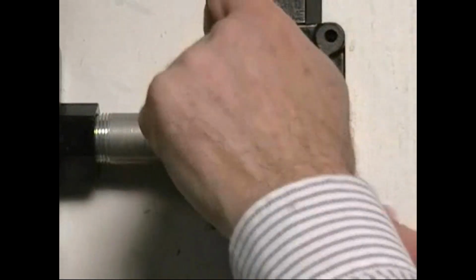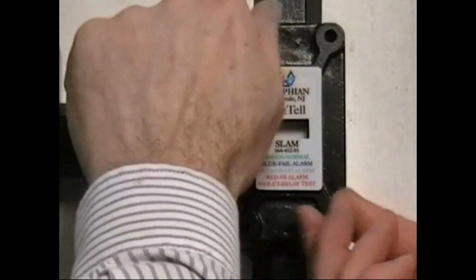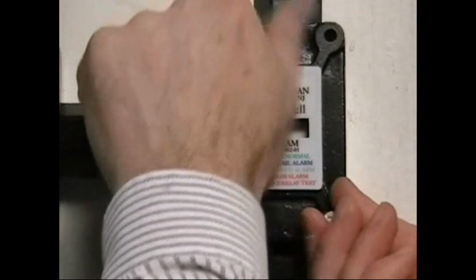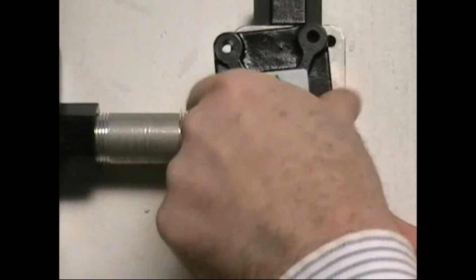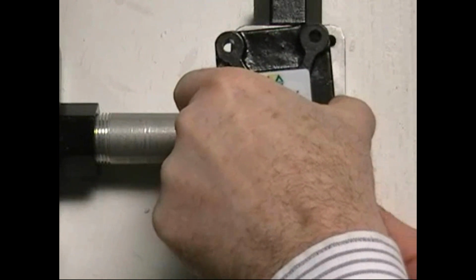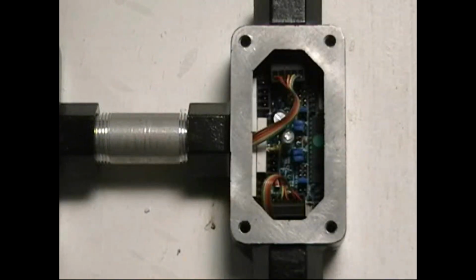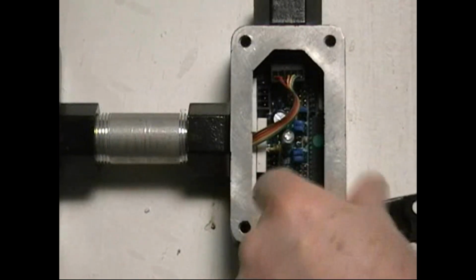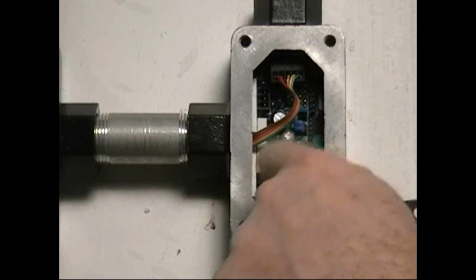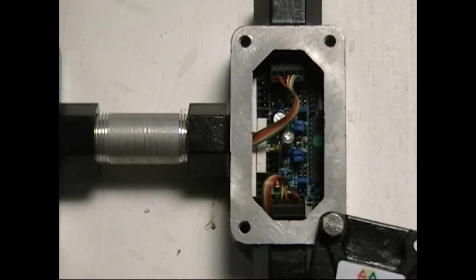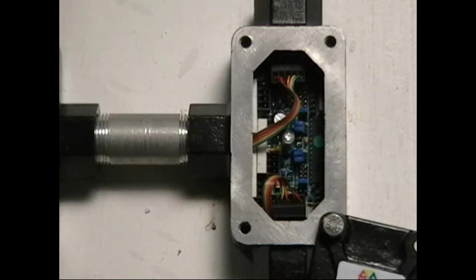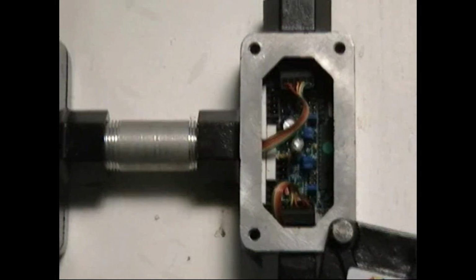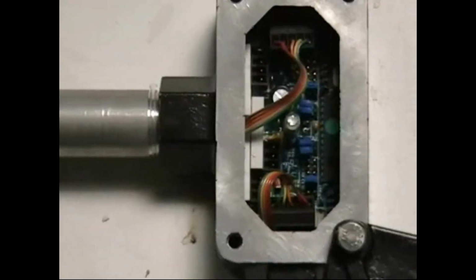Before actually using the GazTell system for the first time, the user must set up the components to operate to the specifications of his application. To begin the setup, declassify the area if it's installed in a hazardous location. Then remove the power from the system. Remove the four 7/16" bolts that secure the SLAM cover using a wrench or socket. As a tip, I often use one of the bolts and hang the cover off the side of the housing to prevent misplacing or damaging the cover.